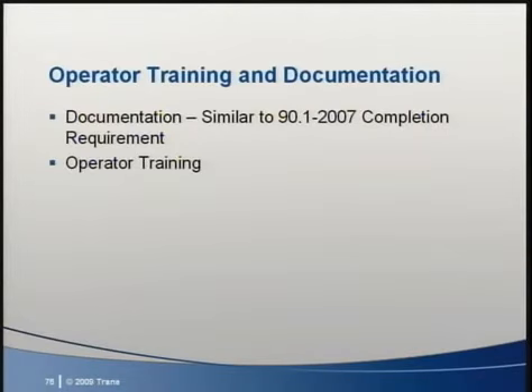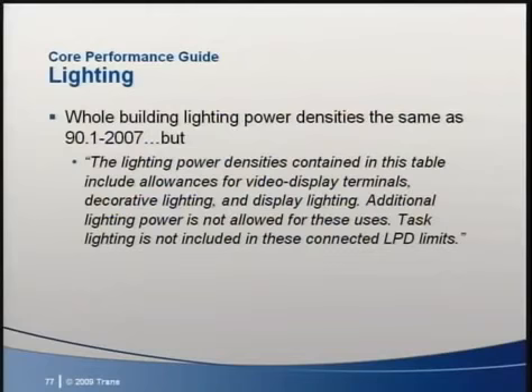This is an important requirement because the operators need to know how the building was intended to operate in order to run it efficiently. In Table 2.8.1 of the Core Performance Guide, the lighting power densities allowed are the same as 90.1 2007 for many building types. However, there's an important note that explains that in the Core Performance Guide, these power densities include video display terminals, decorative lighting, and display lighting. So the actual installed lighting power for people will need to be lower than the 90.1 2007 allowances.